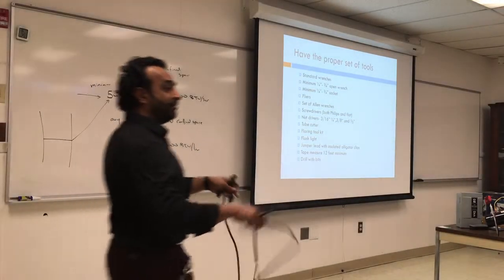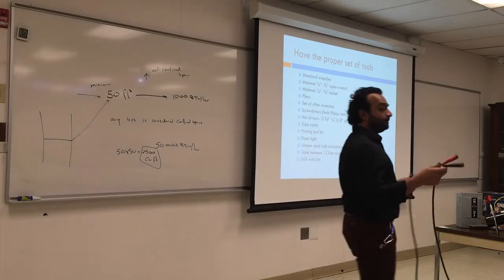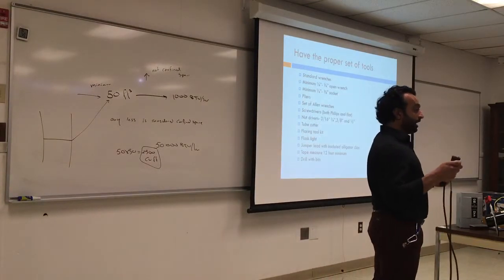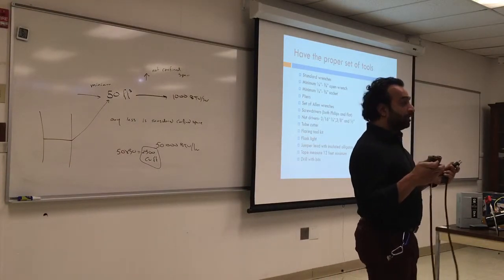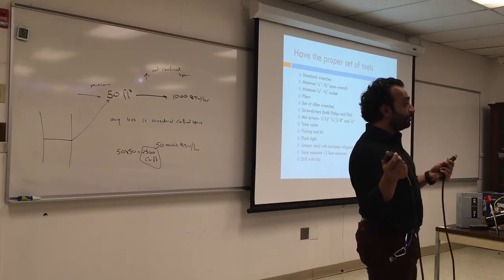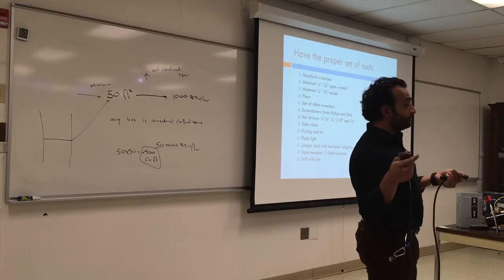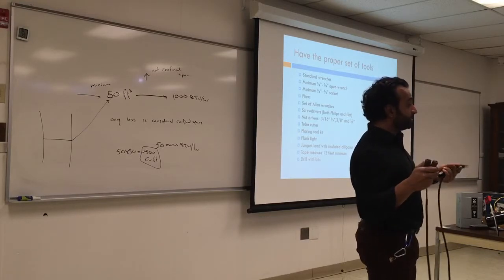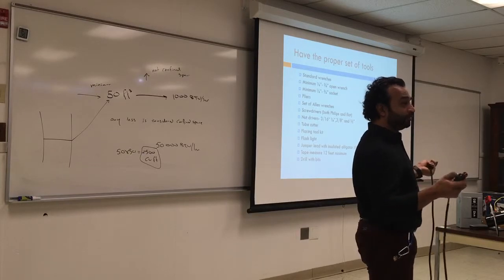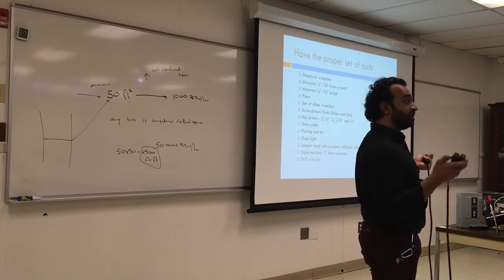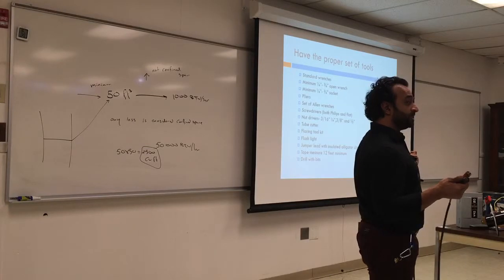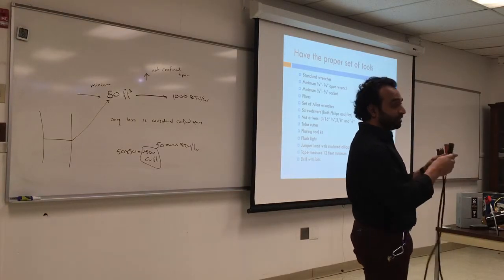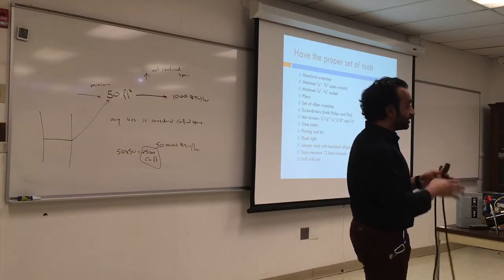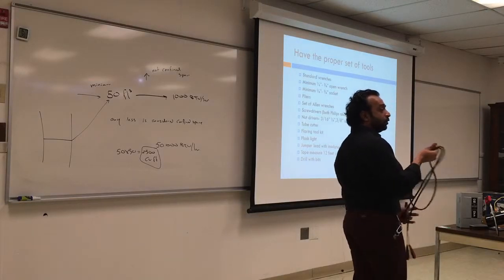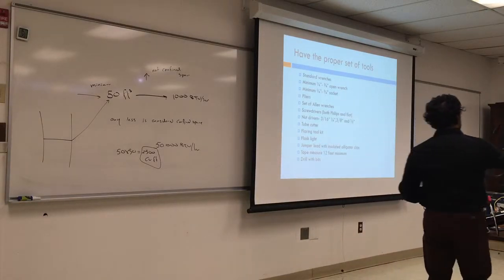So this is something you can buy from Home Depot or any warehouse. And you put those with a power surge cord with a switch, so you can plug it into the motor. You can test the motor by itself, you can test the oil valve, or you can test the igniter. They're very convenient, and make sure they have the sleeves so they do not touch. And again, always keep in mind that you're working around oil and gas, so be careful.